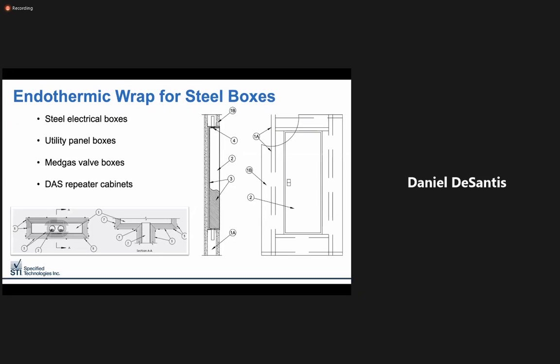It's not just DAS hardware that might require protection. Maybe it's a utility panel for a backup generator or a med gas valve box. Either way, using endothermic wrap is a tested and purpose-built solution for the protection of these items that will meet the performance requirements of the building code for your region. The sketch shown on the right shows both section and elevation views of a typical panel box recessed into a 2-hour rated gypsum wallboard assembly. Endothermic wrap turns this into a 2-hour rated box and adds very little weight to the overall design.